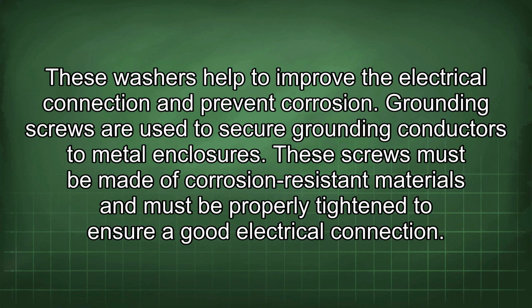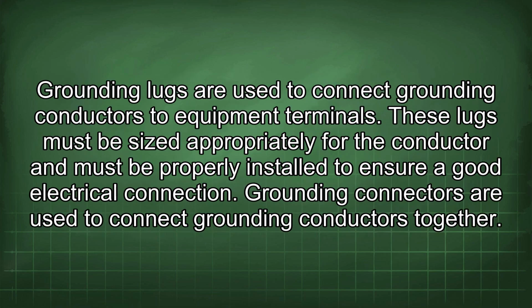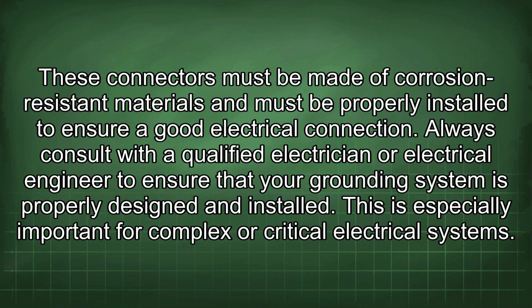Grounding screws are used to secure grounding conductors to metal enclosures. These screws must be made of corrosion-resistant materials and must be properly tightened to ensure a good electrical connection. Grounding lugs are used to connect grounding conductors to equipment terminals. These lugs must be sized appropriately for the conductor and must be properly installed to ensure a good electrical connection. Grounding connectors are used to connect grounding conductors together. These connectors must be made of corrosion-resistant materials and must be properly installed to ensure a good electrical connection.